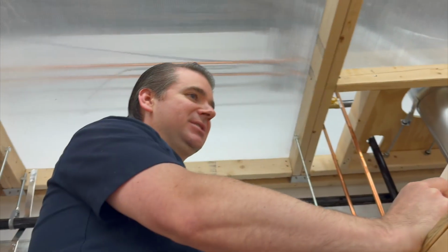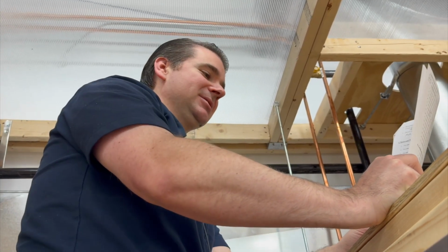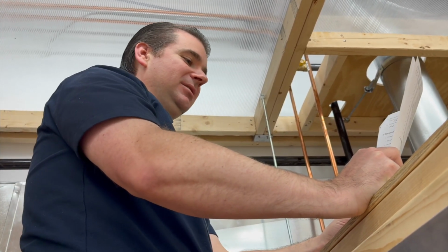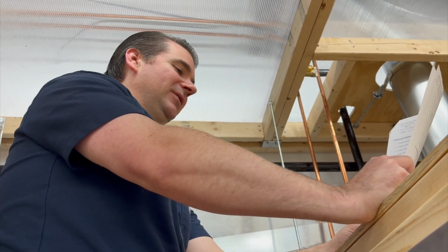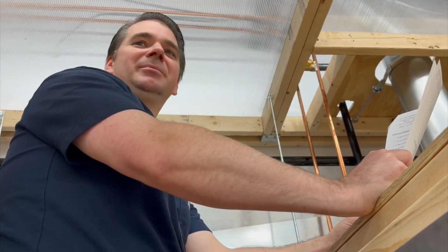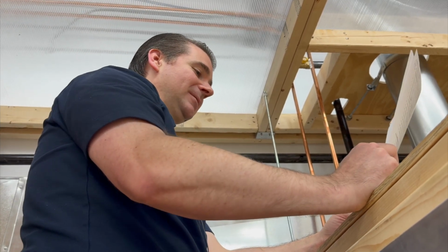Determine the type of existing insulation. We have a small area with some fiberglass batts. Most of the attic has nothing. And for those fiberglass batts, they're about 4-inch batts. Our value for that would be about R13, and it's in poor condition. Recommend insulation for the entire attic.